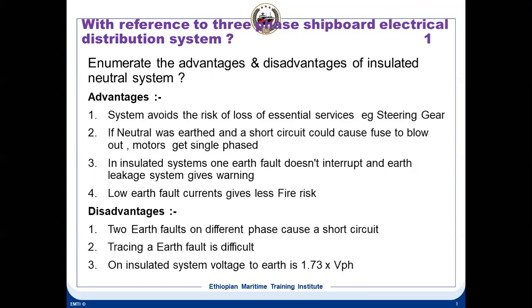We are insulating the neutral, whereas on shore we are grounding the neutral, because on shore it is more for human protection. But on board ship, the critical machinery can't be affected in case of a single earth fault. Second, if the neutral is earthed and there is a short circuit, the fuse may blow off, the motor will become single phased, and the motor may get burnt also. So that is the advantage of neutral insulated compared to neutral earthed.